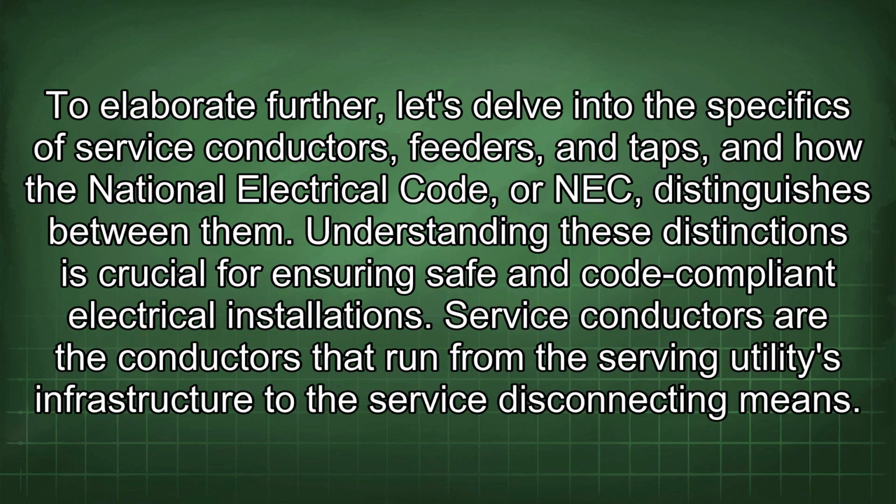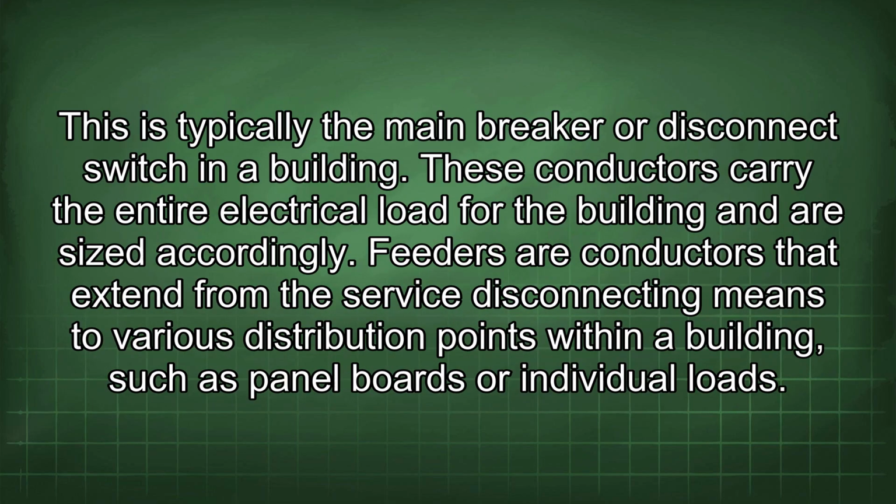To elaborate further, let's delve into the specifics of service conductors, feeders, and taps, and how the National Electrical Code, or NEC, distinguishes between them. Understanding these distinctions is crucial for ensuring safe and code-compliant electrical installations. Service conductors are the conductors that run from the serving utility's infrastructure to the service disconnecting means. This is typically the main breaker or disconnect switch in a building. These conductors carry the entire electrical load for the building and are sized accordingly.